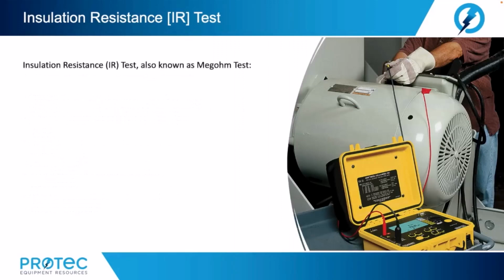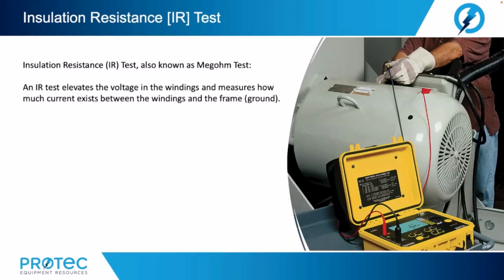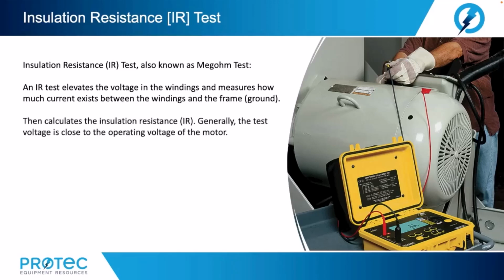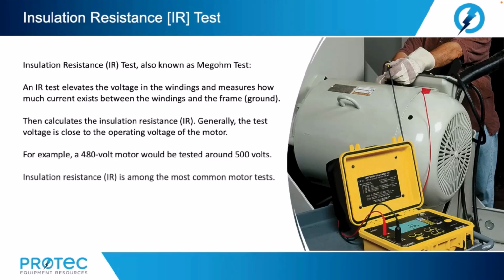Alright, next let's move on to the insulation resistance test. Insulation resistance test, also known as megohm test. An insulation resistance test elevates the voltage in the windings and measures how much current exists between the windings and the frame or ground. Then it calculates the insulation resistance. Now, generally the test voltage is close to the operating voltage of the motor. For an example, a 480 volt motor would be tested around 500 volts.